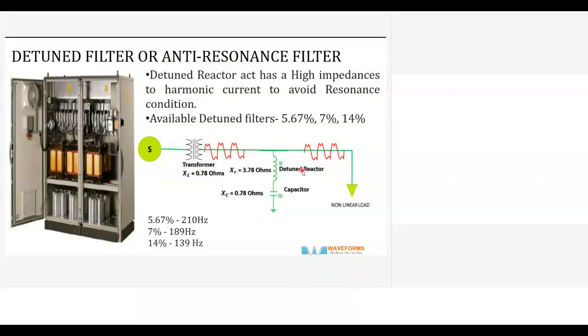When it is away, it forms a high impedance path for that frequency. So it is basically a 7% impedance. The winding will be a little less than the 14%. The higher the percentage of impedance, the more the winding and the more the magnetic flux.